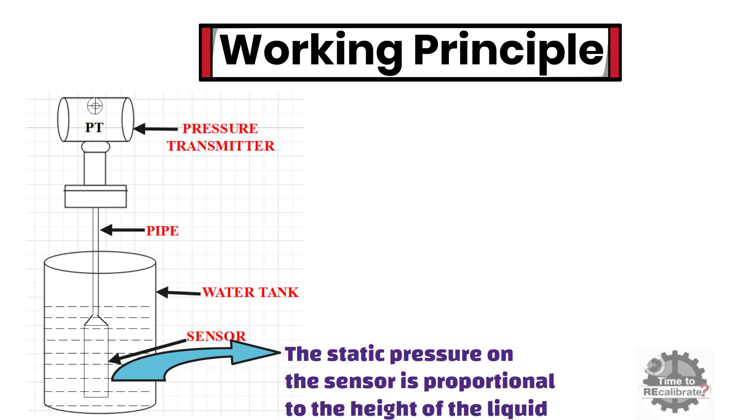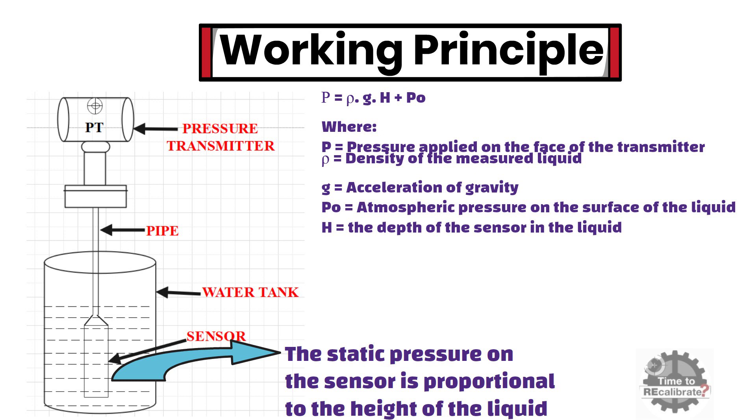For example, when the liquid level sensor is placed at a certain depth in the liquid level to be measured, the pressure is applied on the front face of the sensor. As you can see in this equation, rho is the density of the measured liquid, g is the acceleration of gravity, H is the depth of the transmitter in the liquid, and P0 is the atmospheric pressure on the surface of the liquid.